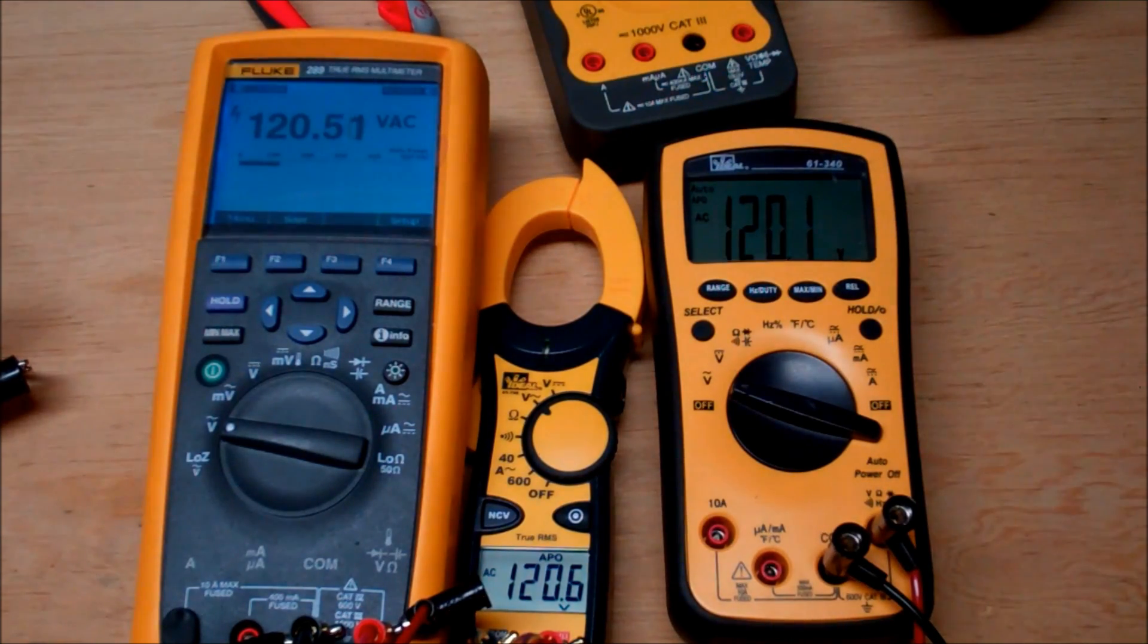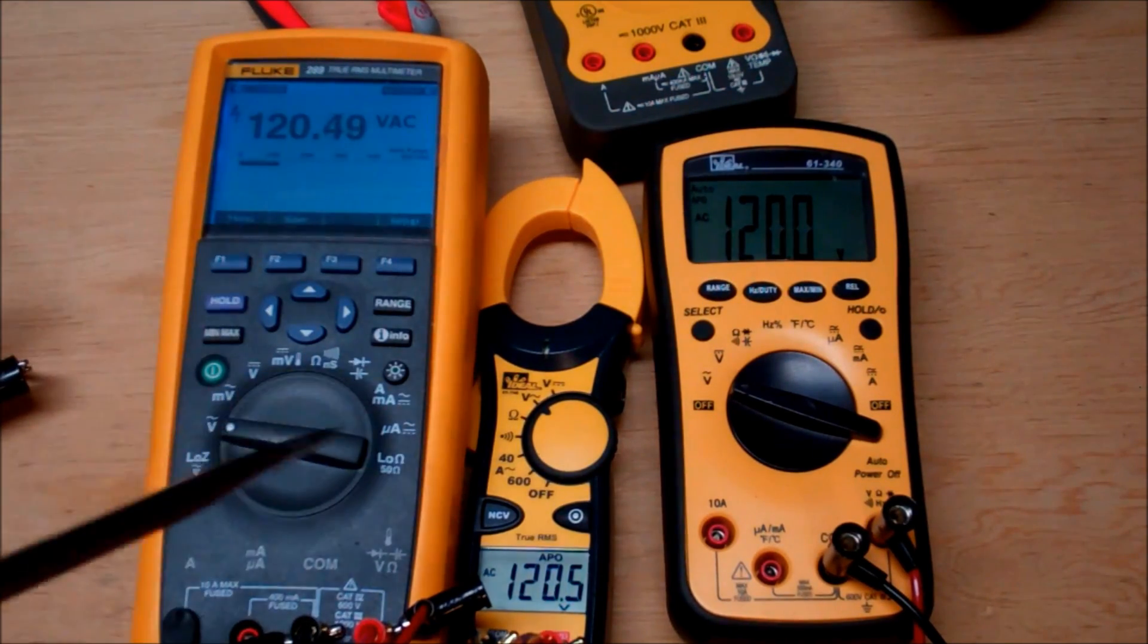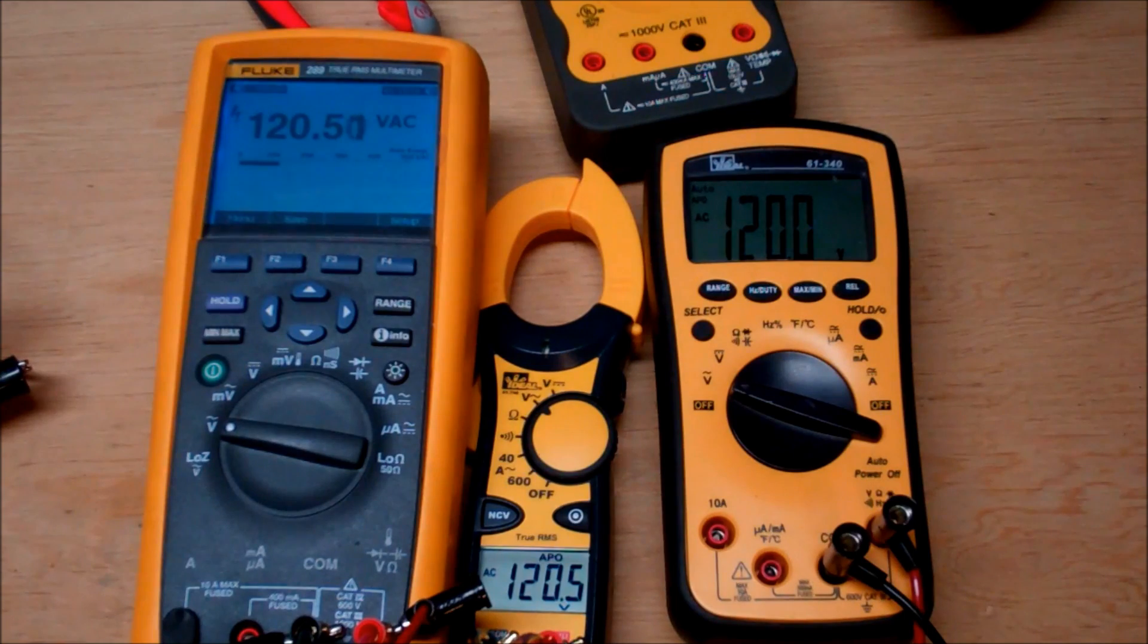Now the 61 340 here is not a true RMS meter. And as you can tell, the reading is not as accurate as what these two are capable of doing. It's an expensive feature to get integrated into your multimeter, but it's well worth it, as you can tell, if accuracy is important to you.